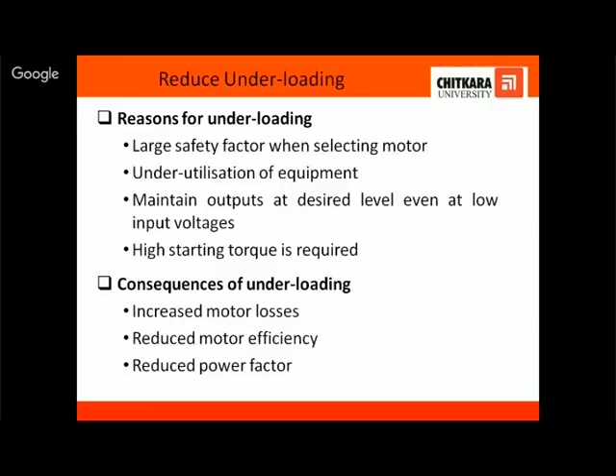Now, why is the motor underloaded? There can be two reasons. One is that when we selected the motor, we kept a large safety factor. This safety factor is good when we are designing buildings or earthing designs and all. But when the motor is designed and we have kept the safety margin, what will happen? We have chosen an oversized motor for a particular application.